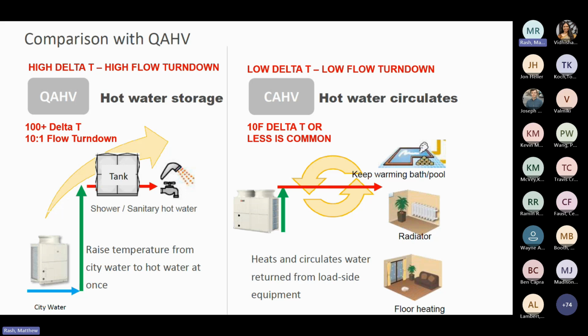It would typically be applied in a multi-pass arrangement, again, because it's low delta T, and you would have options to do return to primary with this, with your storage, and eliminate the swing tank. This has similar nominal heat output, 40 kW, so nominally it's similar to the QAHV product. It doesn't get up to as high a water temperature, up to 165 down to 14 degrees, and then 149 at minus 13. So this is something to watch out for with domestic and colder climates. Certainly if you want to have storage water temps closer to 150 or above, that can be problematic.